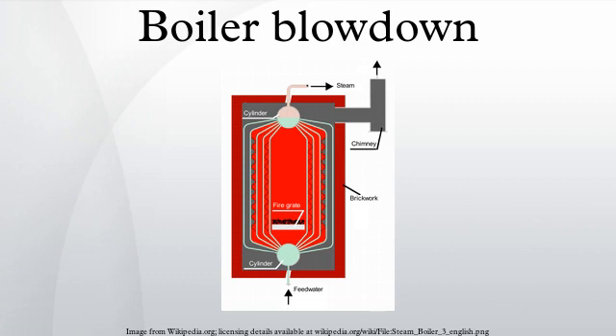Care is taken to avoid trapping scale or rust particles within the valve by reopening a valve to flush the particles through if resistance is encountered when attempting to close it. Bottom blowdown valves are often rebuilt or replaced whenever the boiler is taken out of service for maintenance.